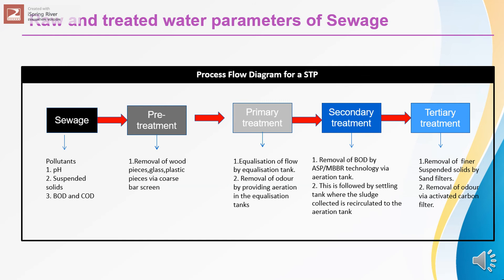Let me throw more light on this sewage treatment plant with the help of this process flow diagram. As you can see here, sewage has a slightly acidic pH, and it constitutes suspended solids and BOD and COD. In the pre-treatment stage, the wood particles, glass particles, and plastic particles are screened off via a bar screen.